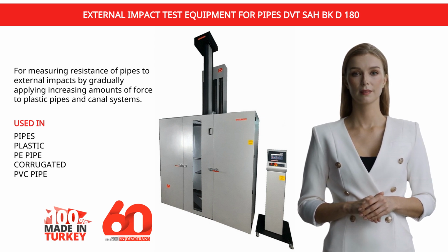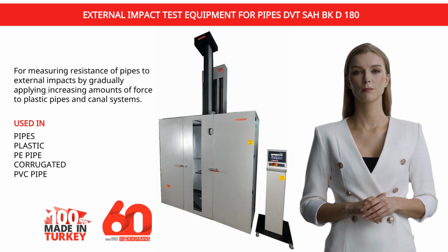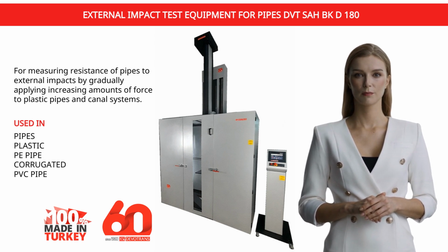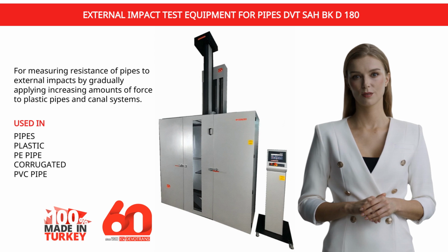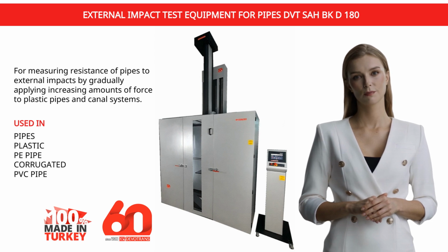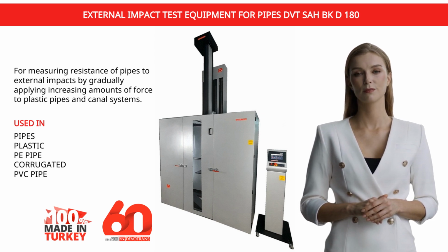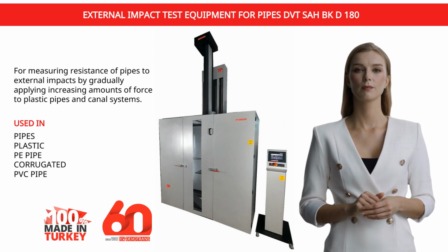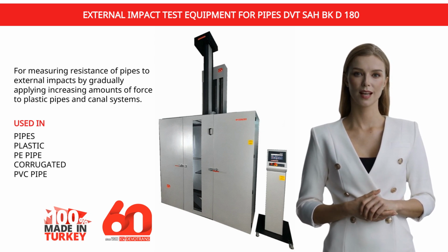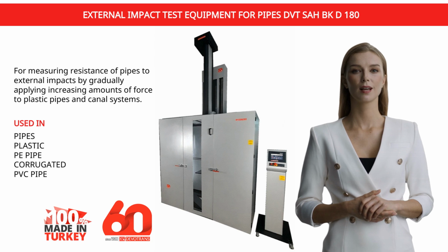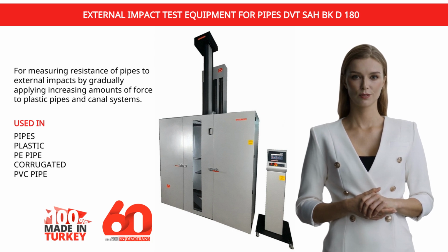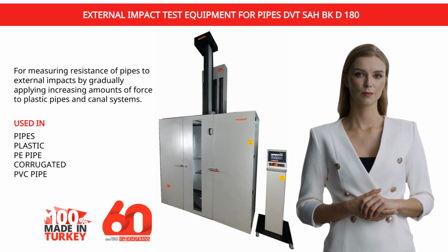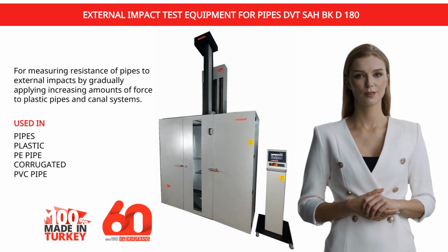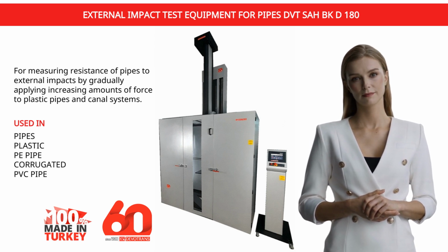forces. It is commonly conducted on plastic pipes, such as PVC, PE, PP, but it can also be applied to metal and composite pipes. The purpose of this test is to observe how the pipe reacts to external mechanical impacts it may experience during installation, transportation, or use, and to evaluate the quality of the material. Here are the detailed steps of the test.